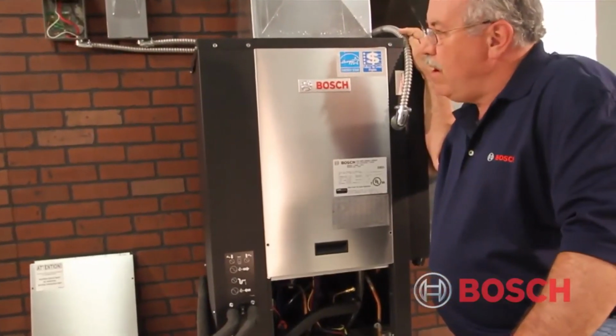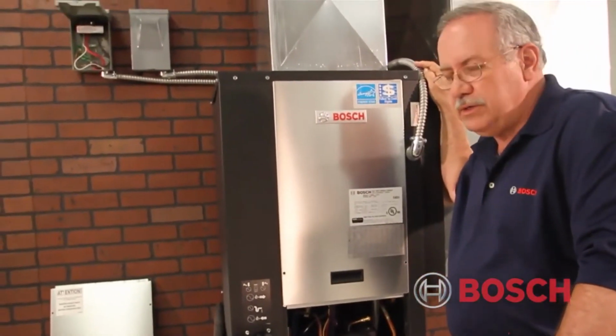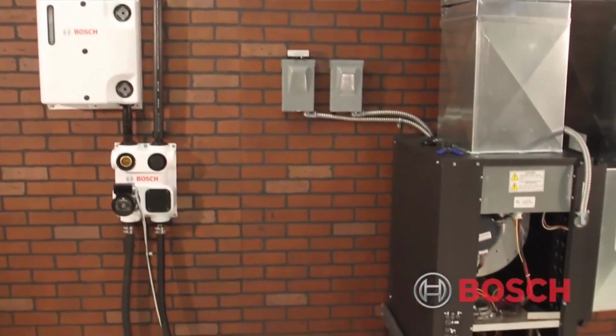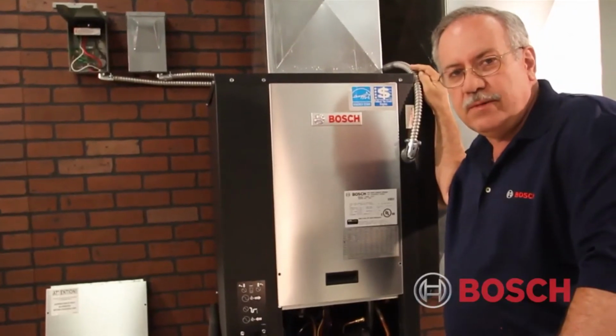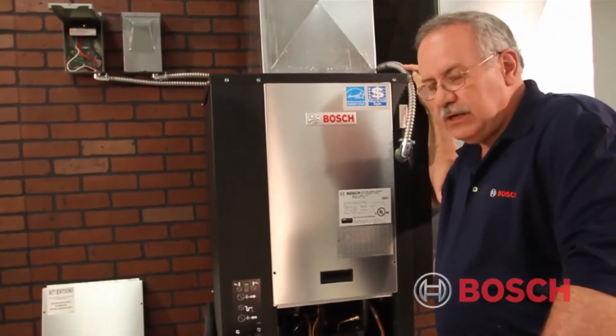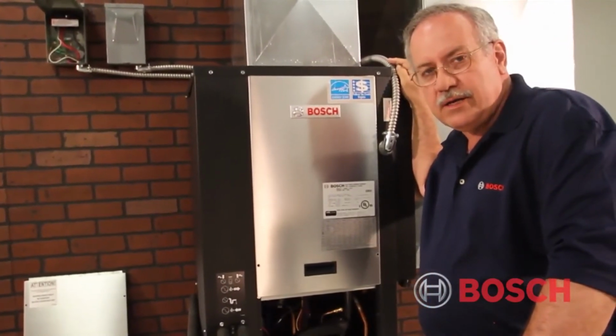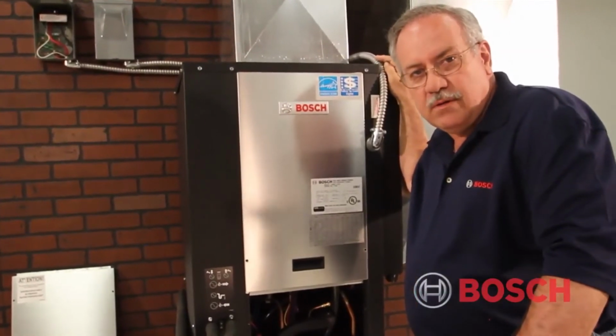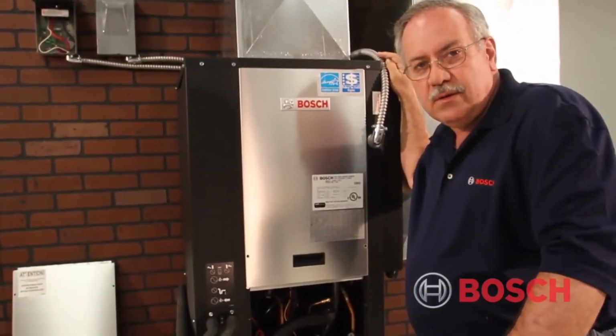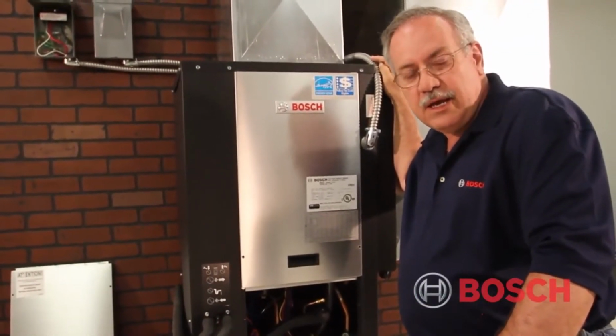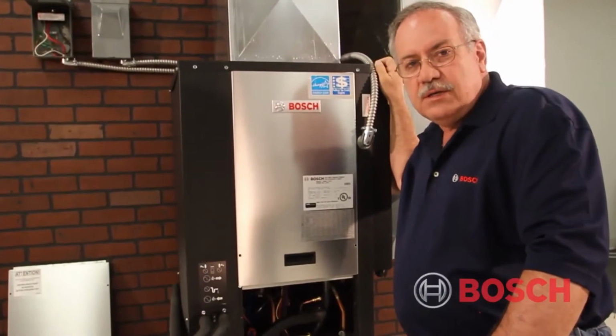Okay, so now we're going to discuss actual waterside diagnostics. With a Bosch geothermal heat pump, such as we have here, this TAO25, water is everything. Without the proper gallons per minute flowing through the coaxial heat exchanger and therefore into the ground heat exchanger, we will have no effective heat transfer. We will have no value. So what we've got to do, we made sure, hopefully, that we have the right electricity and we also have the right airflow. So the next thing is to check the waterside diagnostics.